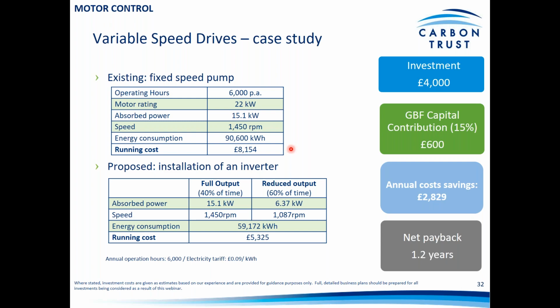If that same system was to be used with an inverter, what you'll see is that for 40% of the time it runs at full output, still at the same 15.1 kilowatts. The speed is the same at 1450 RPM, but for 60% of the time it's able to run at a much reduced power of 6.4 kilowatts, and again at a lower speed of 1087 RPM. So that ability to sit back at a much lower level of operation for much of the time gives an energy consumption for the year of just under 60,000 kilowatt hours.